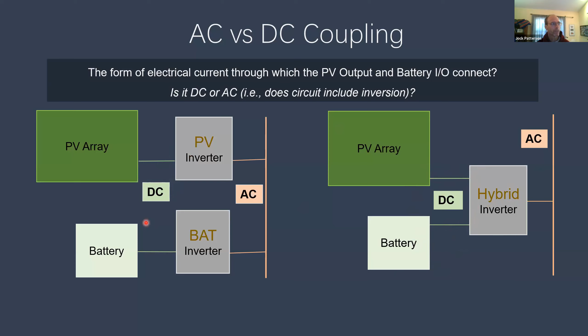Battery systems, I'm going to go through this briefly because we're not focused on this. Just know we have this for AC and DC coupling. As I explained, we use high voltage batteries. It's more efficient connecting and gives greater flexibility. If you can't put your battery and your inverter in the same spot, and this is not uncommon, I just looked at a site in Colorado where the inverter is outside because our inverters are NEMA 4X rated, so they could be in that environment. But the lithium ion battery doesn't discharge when it gets really cold out. So they put that in the basement.